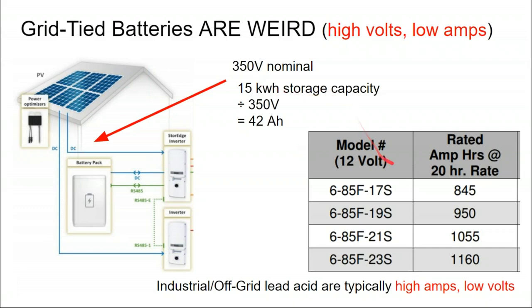Whereas at home, even if you wire up a 12 volt flooded lead acid into a 48 volt bank, you're still having to get it up to 120 volts or 240 volts for your residential service. It's more efficient to take high voltage solar and keep it in a high voltage battery, then deploy it at a high voltage electric service panel, whereas the lead acid low voltage design parameters are more geared around motors that only needed that low voltage.